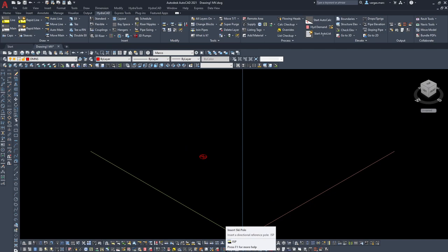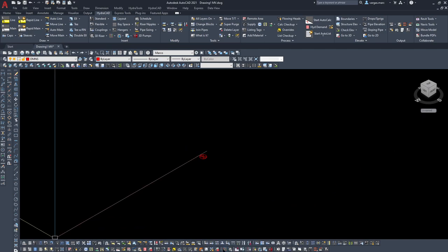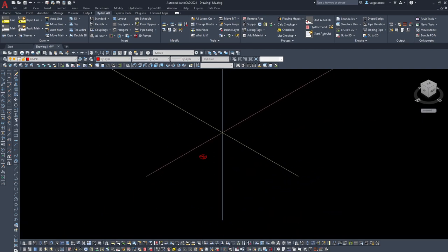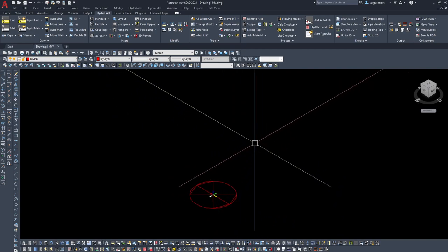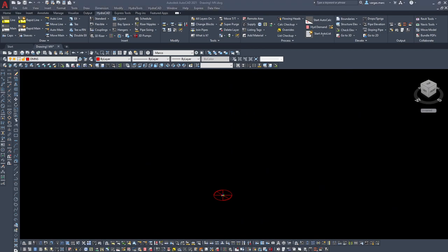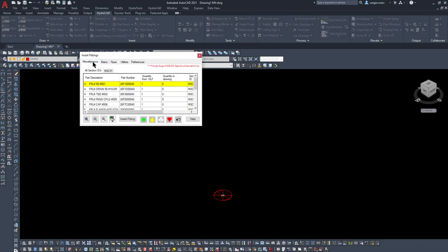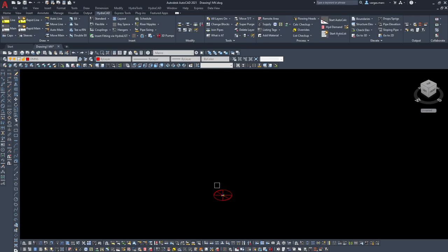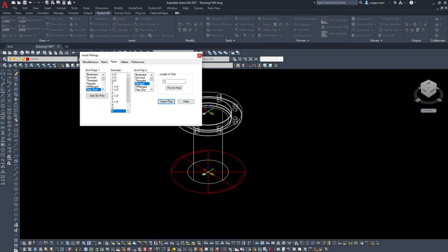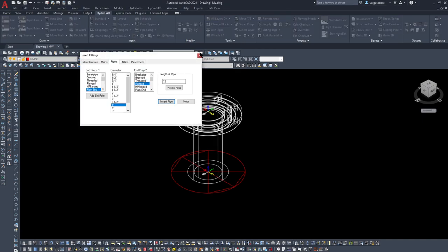We're going to insert a ski pole. The shortcut command is ISP in case you're not familiar with the toolbars. I'm going to insert it right to the center of this guy — there's our ski pole. The only thing I tend to draw using the 3D riser command is just the starter flanges. I'll go into pipes and draw a 6-inch pipe with plain end and flange end, 12 inches long, and insert it to the ski pole. Then I'll also insert a 4-inch plain and flanged 12-inch piece.